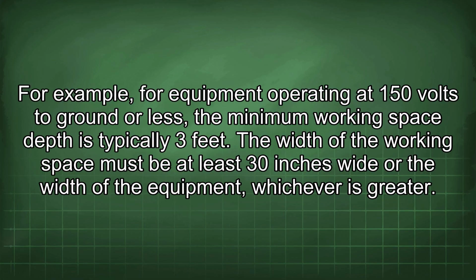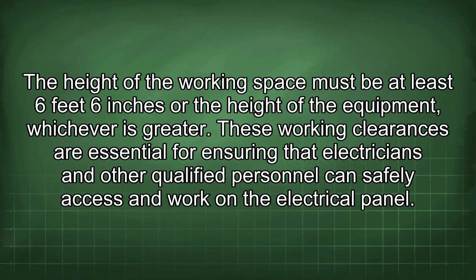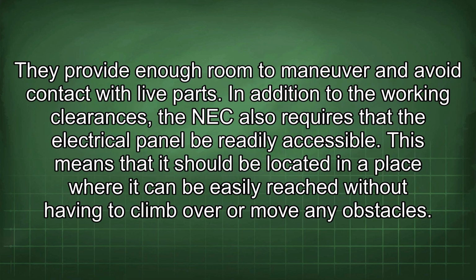the equipment, whichever is greater. The height of the working space must be at least 6 feet 6 inches, or the height of the equipment, whichever is greater. These working clearances are essential for ensuring that electricians and other qualified personnel can safely access and work on the electrical panel. They provide enough room to maneuver and avoid contact with live parts.